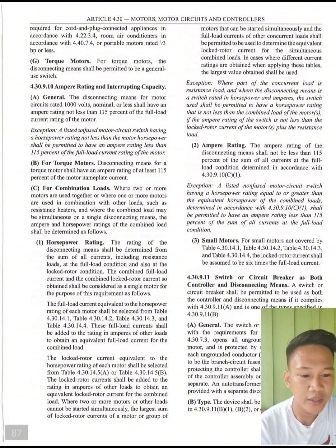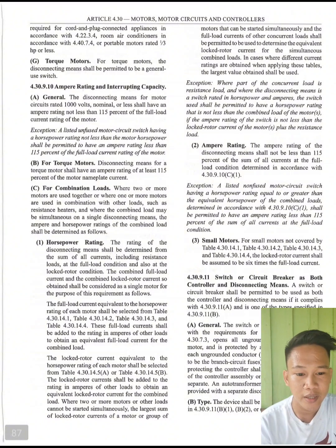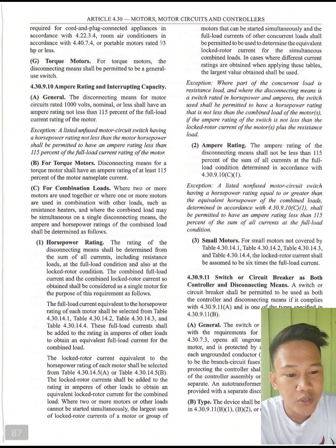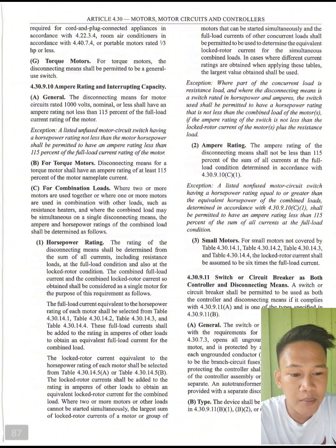Second, we have ampere rating. The ampere rating of the disconnecting means shall not be less than 115% of the sum of all currents at the full load conditions determined in accordance with 4.30.9.10 C1. Exemption: a listed non-fused motor circuit switch having a horsepower rating equal to or greater than the equivalent horsepower of the combined loads determined in accordance with 4.30.9.10 C1 shall be permitted to have an ampere rating less than 115% of the sum of all currents at the full load condition.